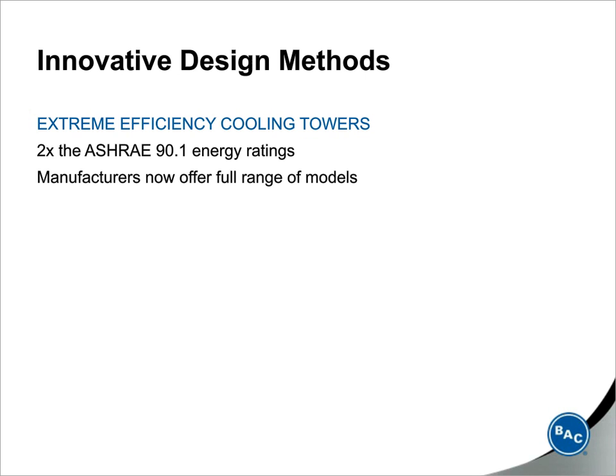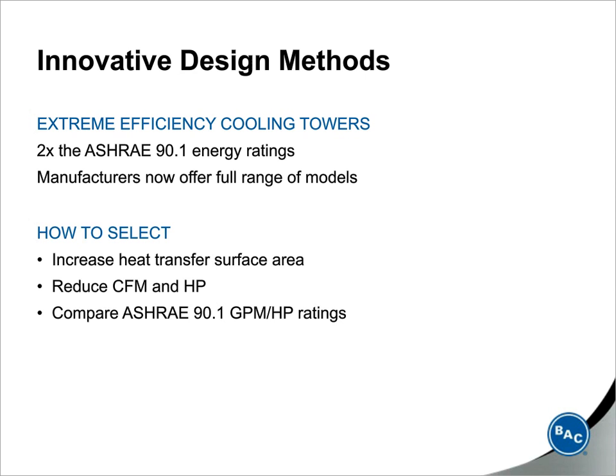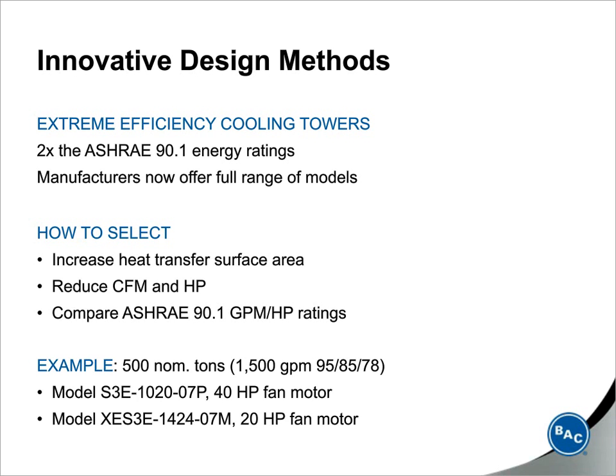And because of the fan laws, you can really achieve some really great energy reductions since energy usage equals the fan speed to the third power. So once you enter your conditions into the manufacturer's selection software, you can compare the ASHRAE 90.1 energy ratings along with the payback to select a cooling tower that offers the lowest total cost of ownership or that meets your needs. And as an example, let's again look at a 500-ton system. The model with the lowest first cost can do the required performance by using a 40 horsepower motor. However, by selecting a model that has a 20% higher first cost, you can achieve payback in just over 1 year.